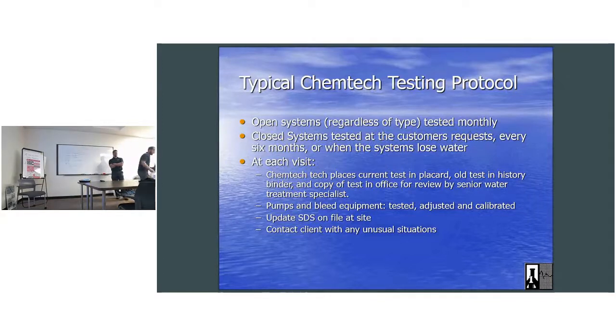I moved a system out at Covington Multicare. They moved an MRI chiller from right outside, across the parking lot, to right up above it. So that was all ethylene glycol, and I had to capture it. This is really critically important with ethylene glycol. You can dispose of it, or recycle it if it's above 15%. If it's somewhere between 8% and 15%, you have to use solidification.